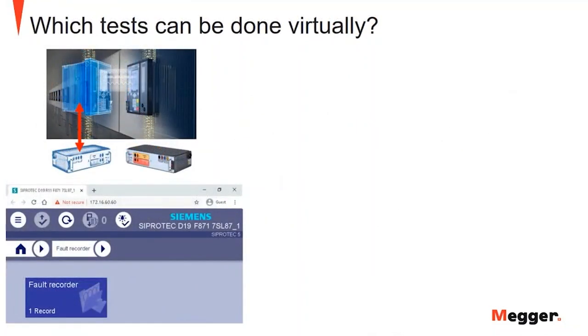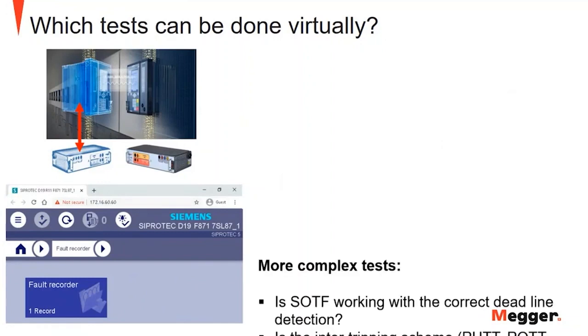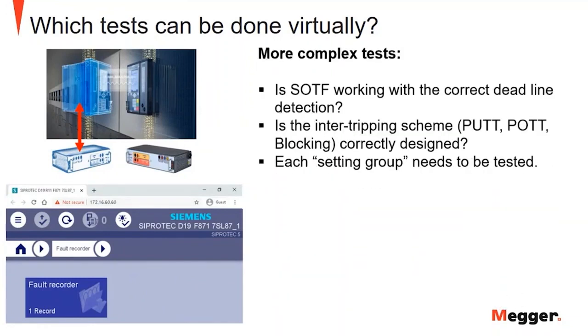Where we need to investigate the internal disturbance record of the protection relay is for verifying more complex tests, like the switch-on-to-fault logic, which can be quite tricky, dedicated with the dead line detection or not. Some settings can be tricky as well. This is not one shot. These are 3 or 4 or 5 tests you have to do.